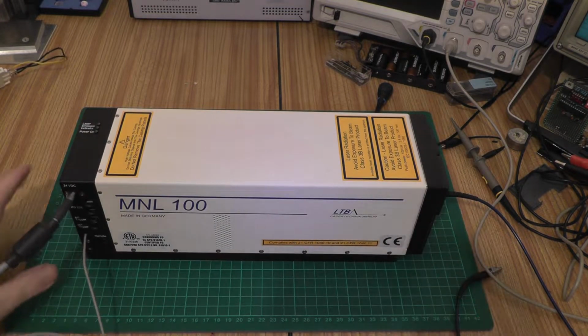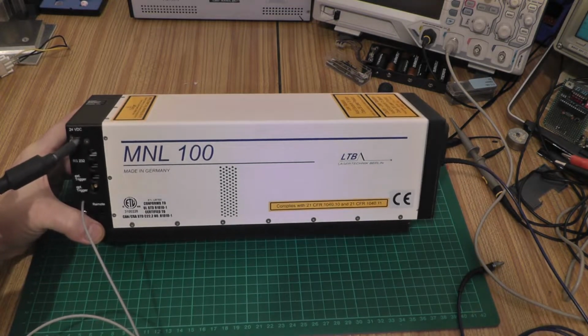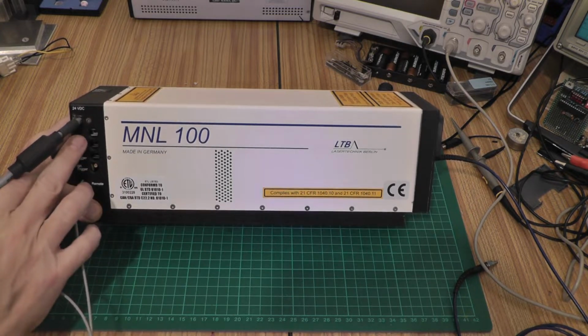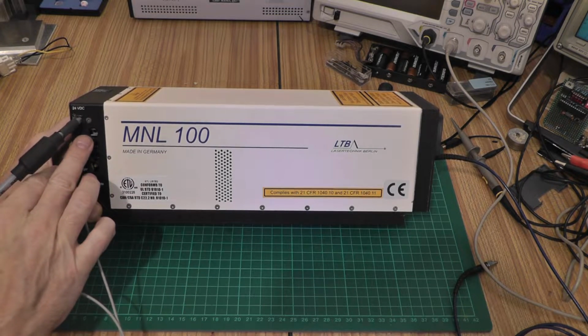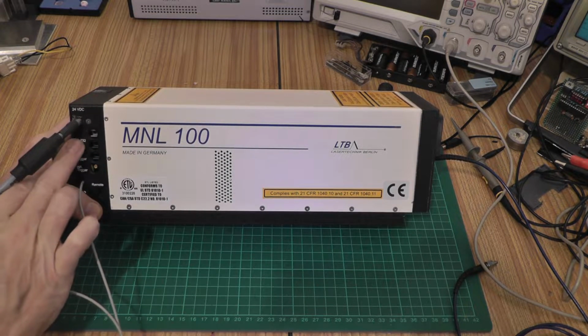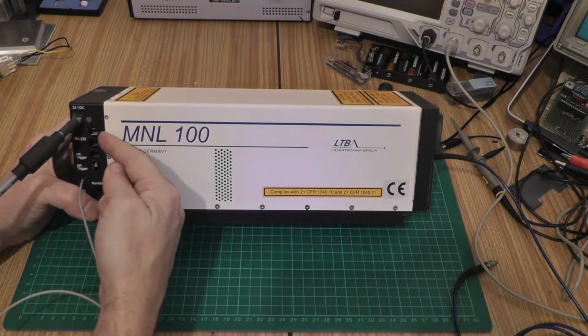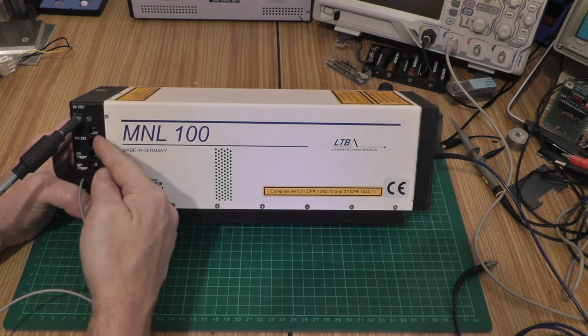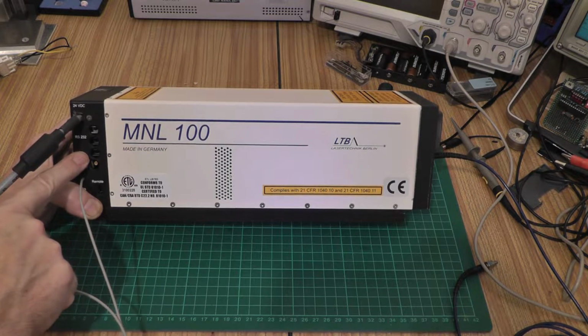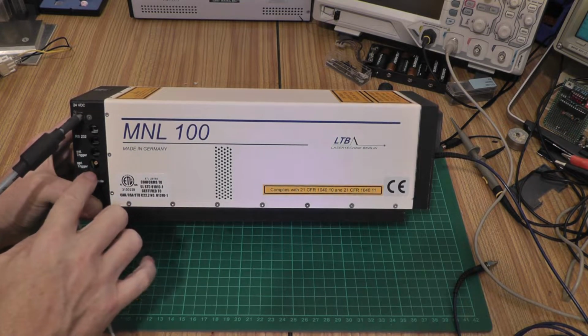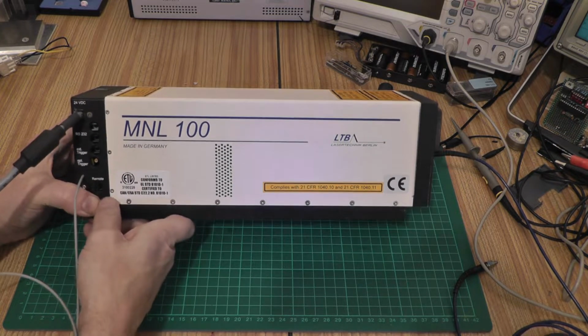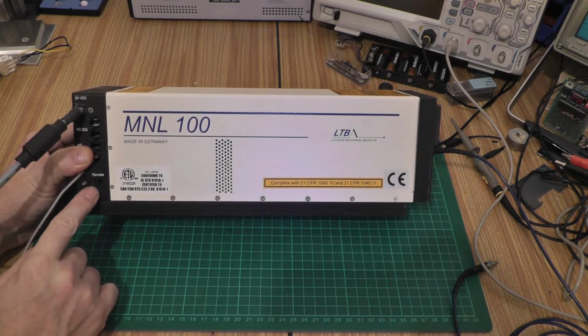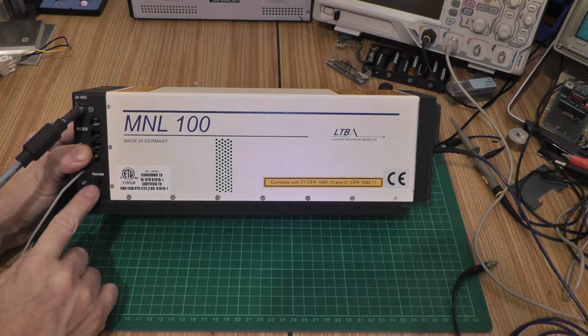This is a really modern nitrogen laser design. If we tilt it up so that we can see, we've got a few holes down the side here. These are actually fiber optic couplings. The top two are for RS-232, so we've got transmit and receive over fiber optic. We've got a fiber optic external trigger. We've got an optional trigger in, and then we've got a USB socket. It's an old style USB socket that says remote on it.